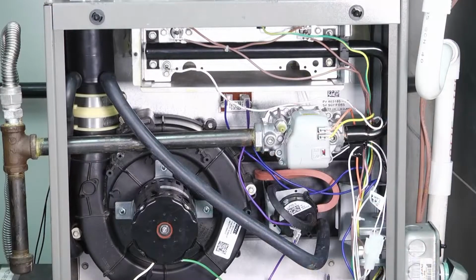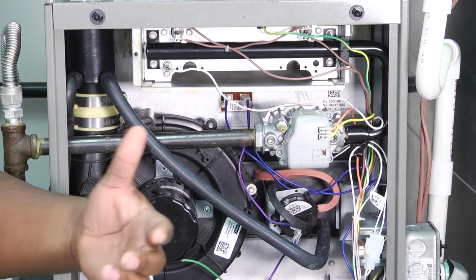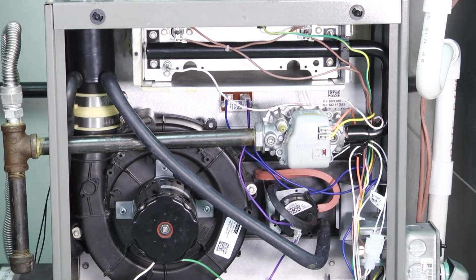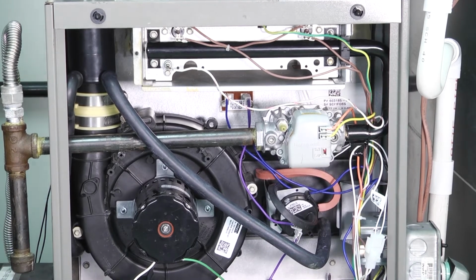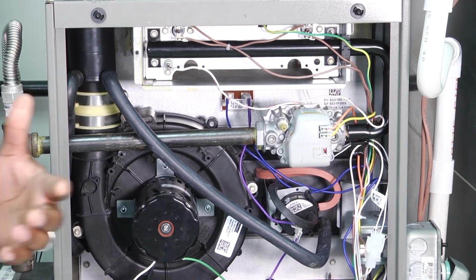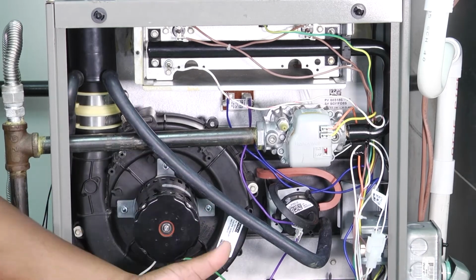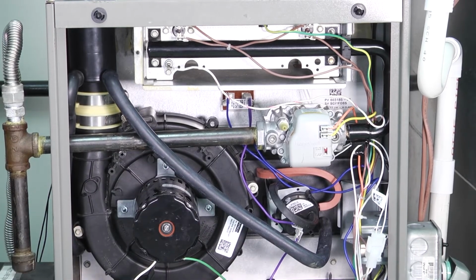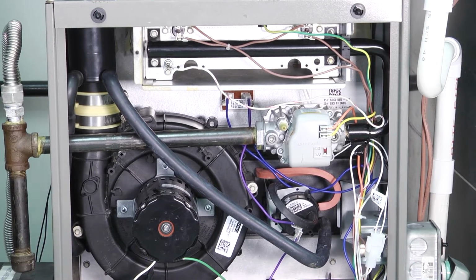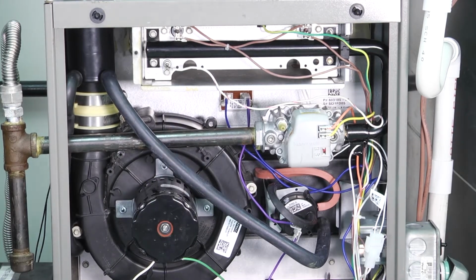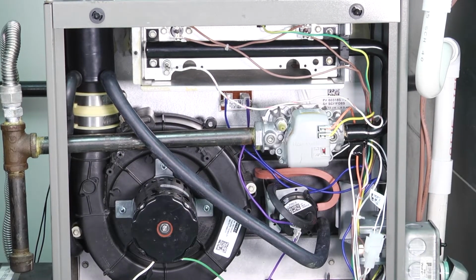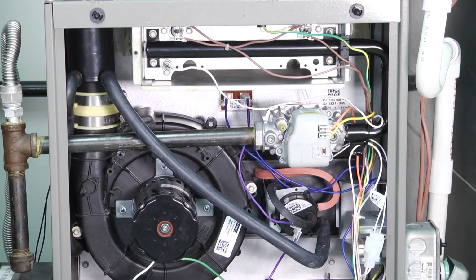Once we move on from the flame sensor, we want to check our capacitor and make sure it's operating within manufacturer specs. If it isn't, we might have an ECM motor, and we'd need to use an ECM motor tester to check that. All of these devices can be bought at your local supply stores, and they're great things for a technician to have in his tool bag.